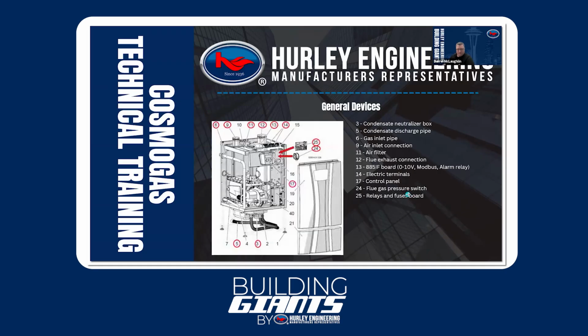Yep. So just a few more items here quickly to show you. We've already looked at some of this. Exhaust connections, this control board up top, that would be our remote input. So if we're going to control these boilers remotely, that would be our control that enables that. Our block vent pressure switch is mounted right here, easily accessible from the front. And then all of our condensate drainage would be down here. In fact, there's a drain switch. I think we've got another slide that'll show that.